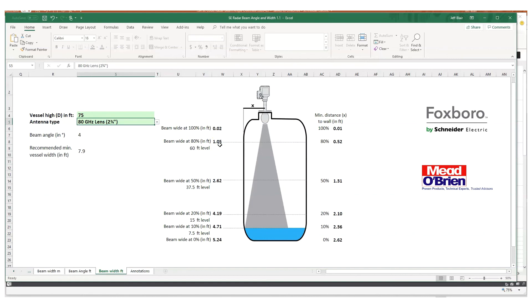So you can actually use these radar beam angle calculators to figure out how big the beam is going to be. Is it going to intersect a thermowell, a baffle, a heating coil, some other obstacle or internal obstacle that may be in the tank. And you can envision how big the beam is going to be and where it's going to go.